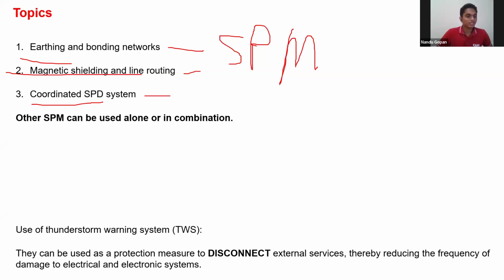The standard also says something like this - I don't agree with it, but I'm putting it for people's knowledge. Your internal systems are going to fail only if the power is on. If you switch off the power, there's not going to be any damage. It says you can use something called a thunderstorm warning system - a device that warns you some time before lightning is going to come. So if you have this system, you can switch off the TV or the data racks. It is not practical, but it is still there in the standard for information purposes.